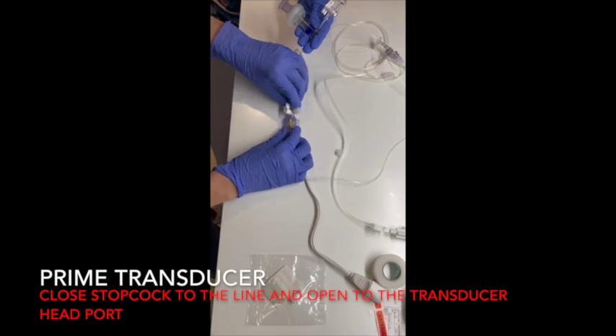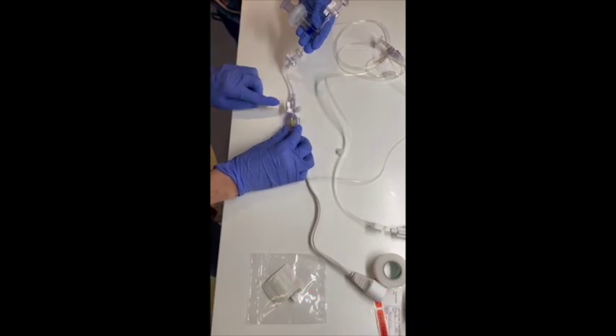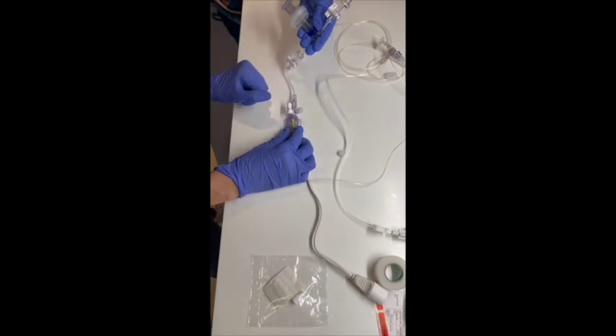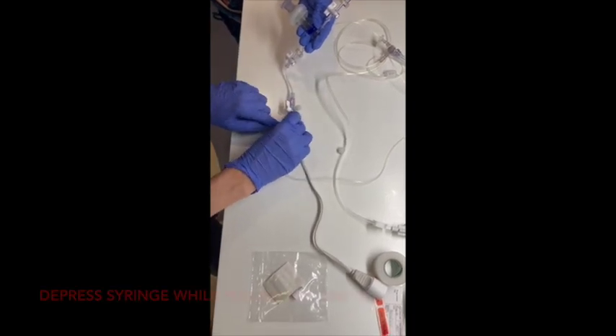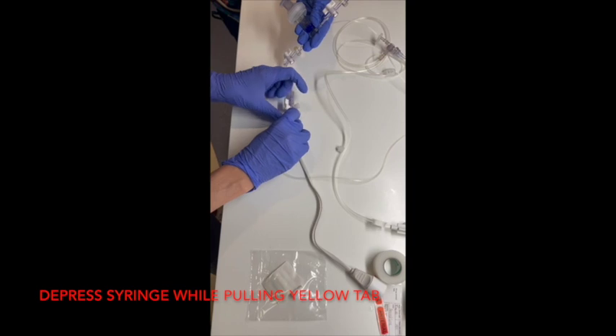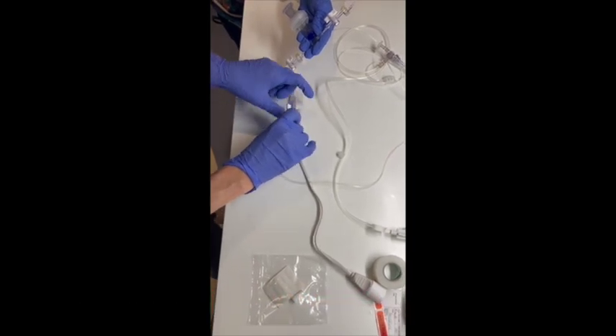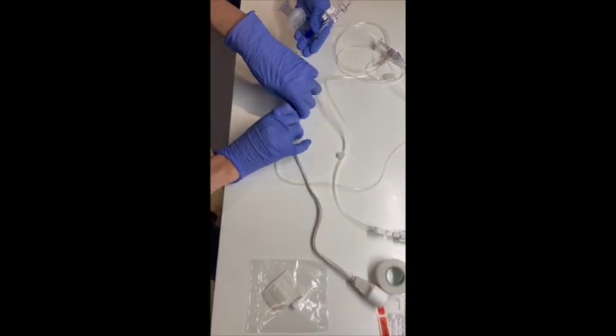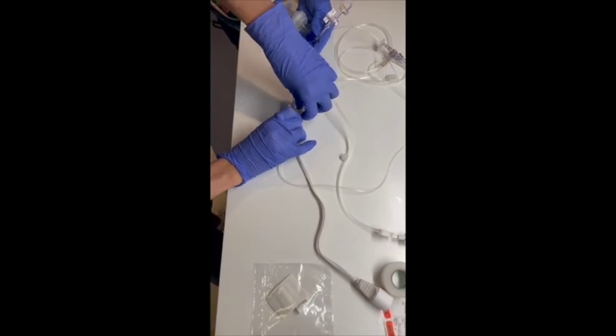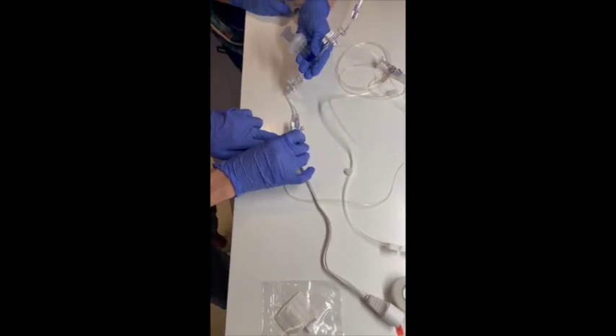Prime the transducer set. While the stopcock is turned off to the line and is open to the transducer head port, depress syringe plunger and provide flow by pulling the yellow snap tab of the pressure transducer while slowly delivering the priming solution. Remove all air from the system during priming.